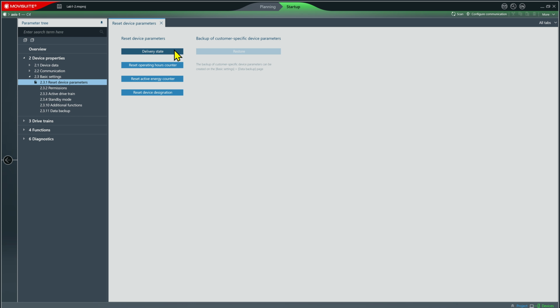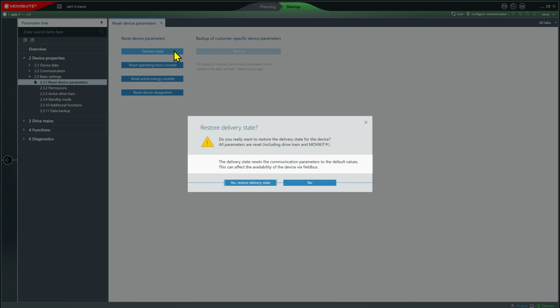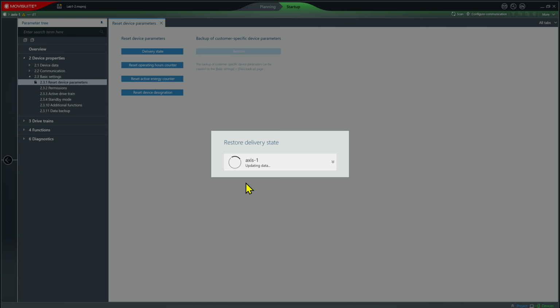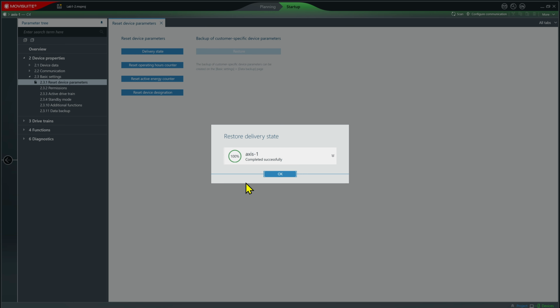Now right here, I've got a button called Delivery State. If I click this, it's going to reset my VFD. Unlike some of SEW Eurodrive's earlier B generation products, which took you at your word the minute you clicked it, in the MOVI-C product line, we double check and say, do you really want to do this? And I do, so I'll go ahead and say yes, restore delivery state. And that's it. My VFD has been returned to the factory default condition.